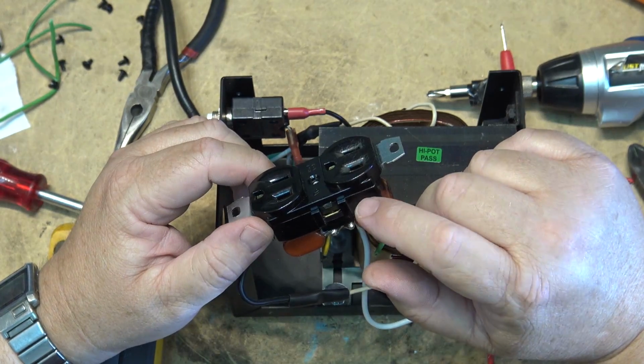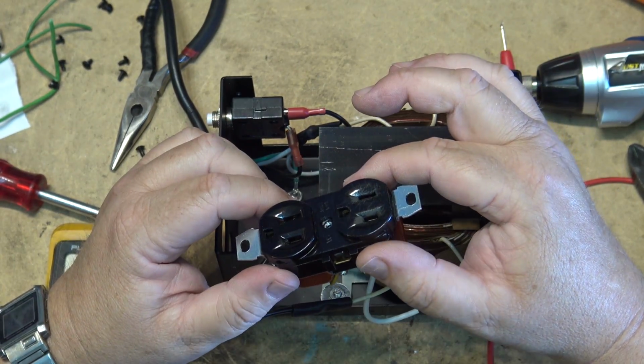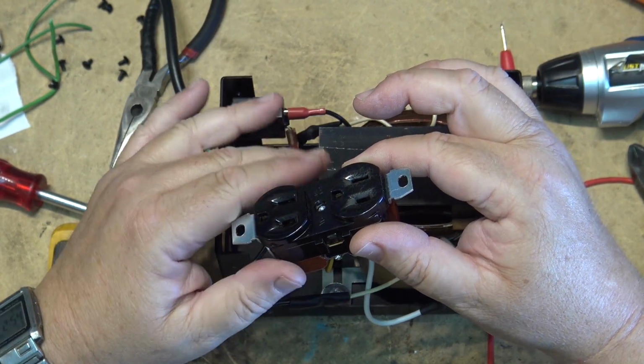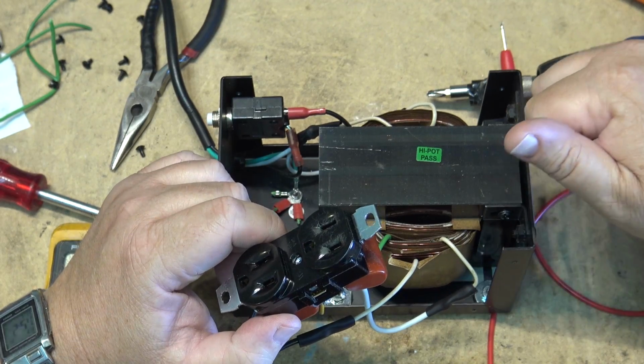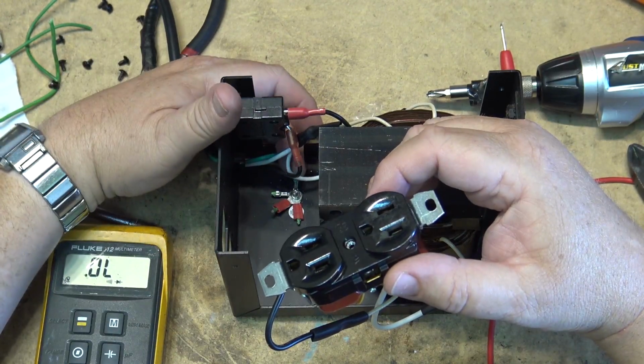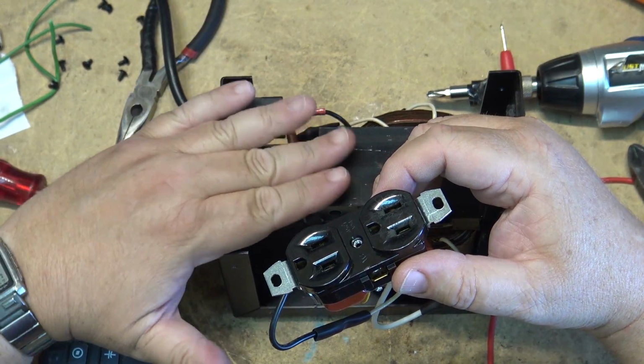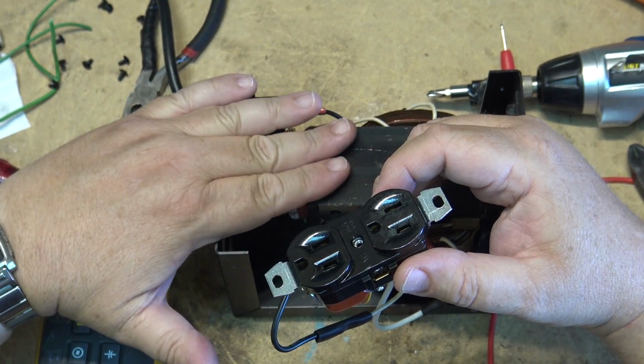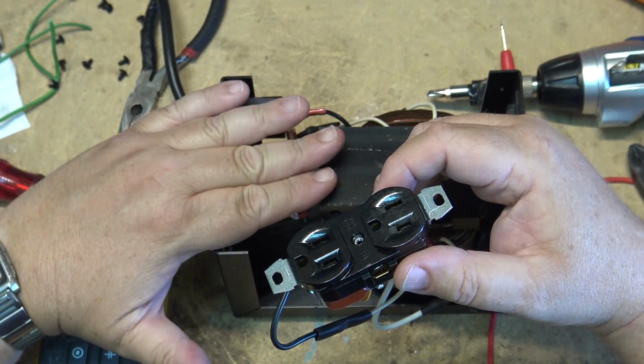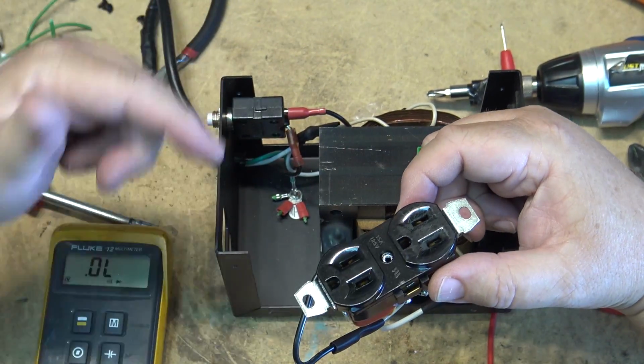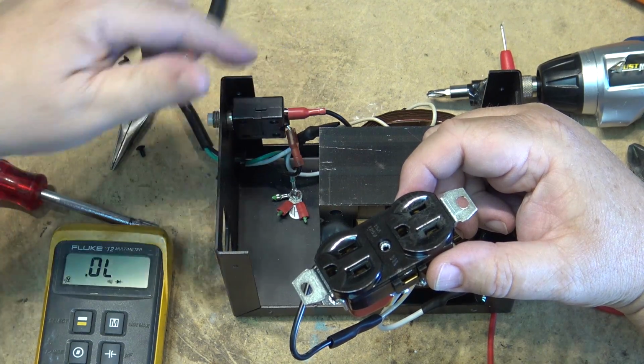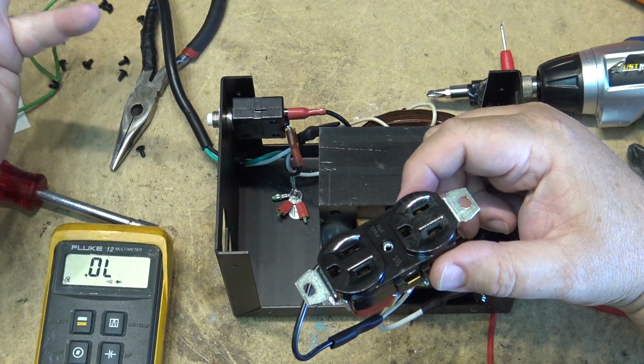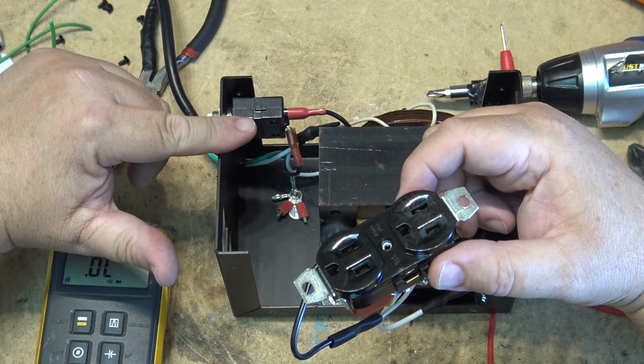If this was mounted in a plastic box, if the outlet was isolated from the metal chassis, I could leave the ground screw and ground wire connected to the metal chassis, and that would keep this at ground potential and never allow this to float if, say, one of the wires were to break off and touch the chassis.